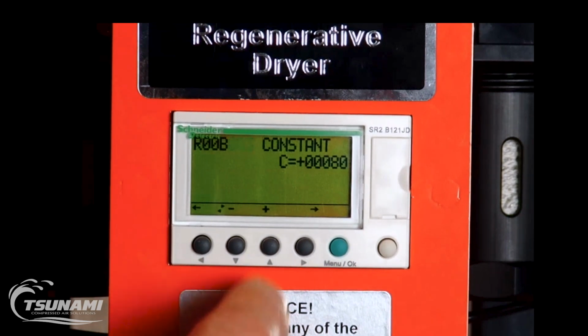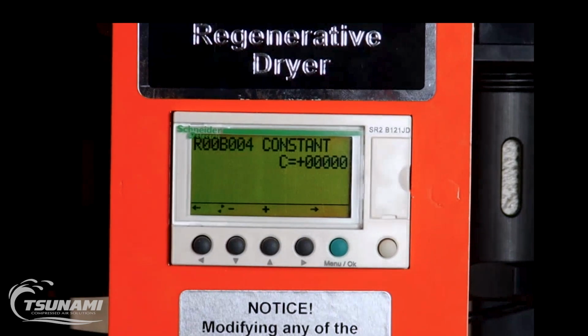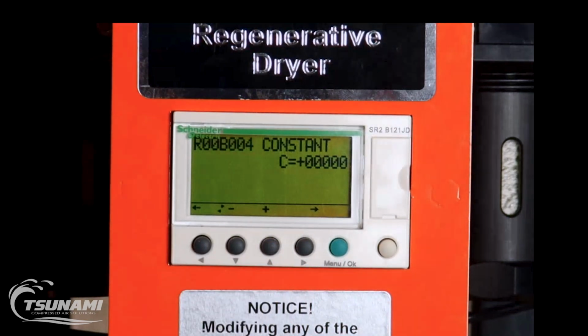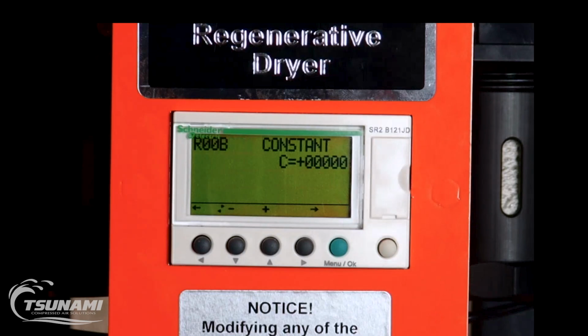And then when we get to 4 and 5, blocks 4 and 5 determine whether or not and how our dryer acts based on those analog or digital inputs going into the PLC. So block 4 has a C value of all zeros. And when we get up to block 5, it has all zeros across the board. And so what that says is the dryer is to run if there is no signal going into the PLC, which we don't have. This system is not hooked up with any kind of digital or analog inputs right now.